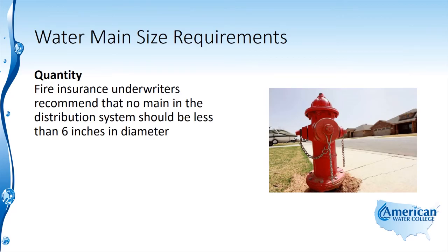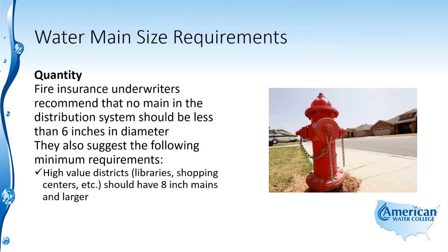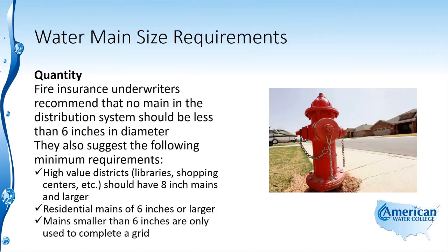Fire insurance underwriters recommend that no main in the distribution system should be less than 6 inches in diameter. Minimum requirements include: high value districts such as libraries and shopping centers should have 8-inch mains and larger; residential mains should be 6 inches or larger; and mains smaller than 6 inches are only used to complete a grid.